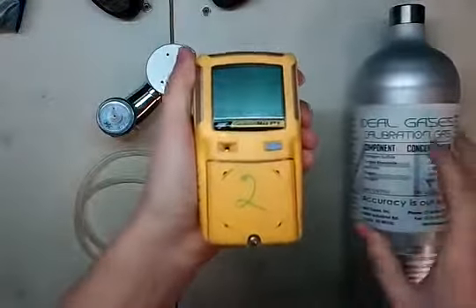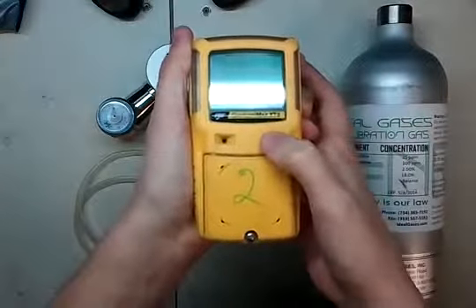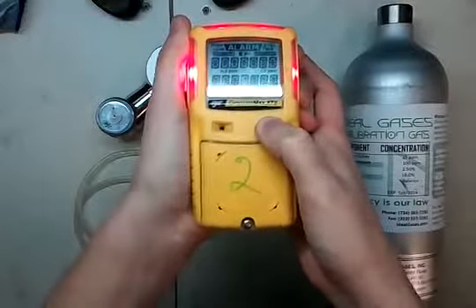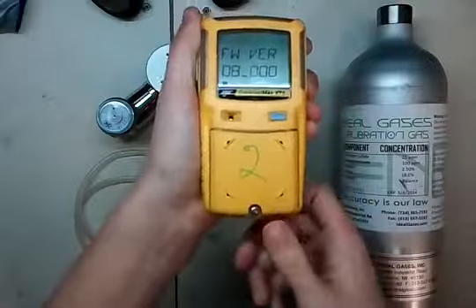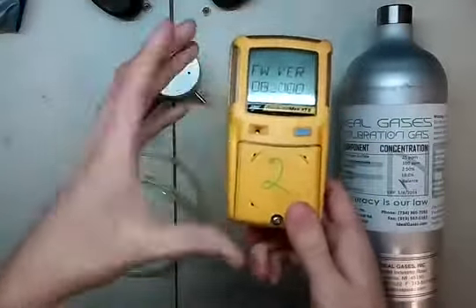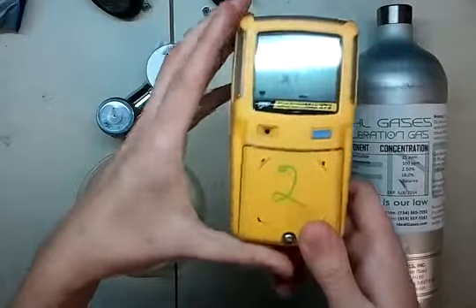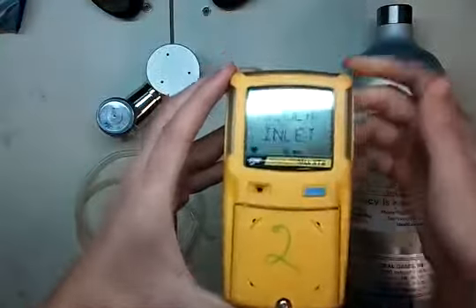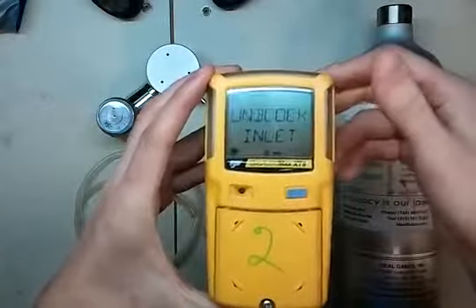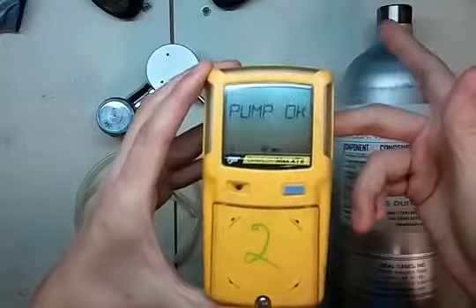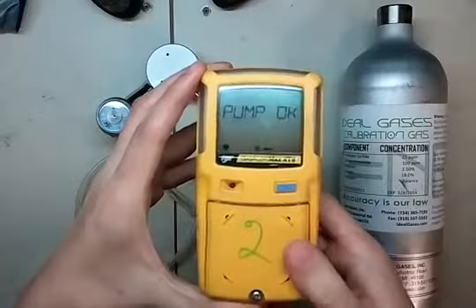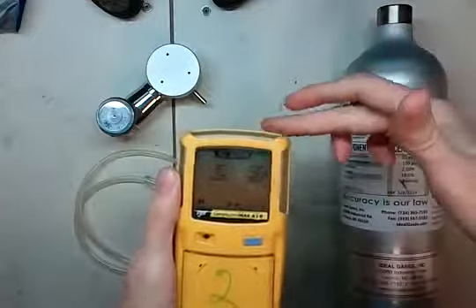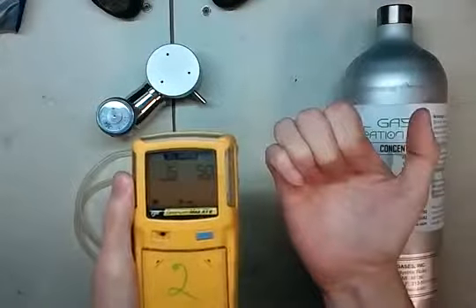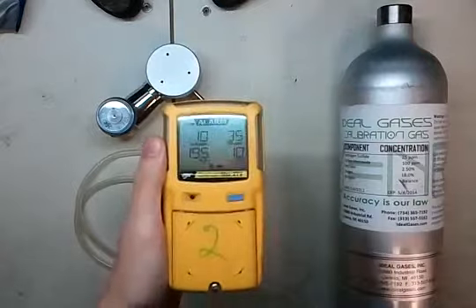So to get started, we're going to press the big button here. Just press and hold it until it beeps, and then go ahead and let go. And it's going to go through a startup check. It says block inlet, so press your finger over there, and then unblock. And now you know you're good to go. Now typically in the field you'll have an adaptation fitting here with a tube, and instead of blocking here you're going to want to block the tube at the end. And that way it knows there's no leaks within your system.